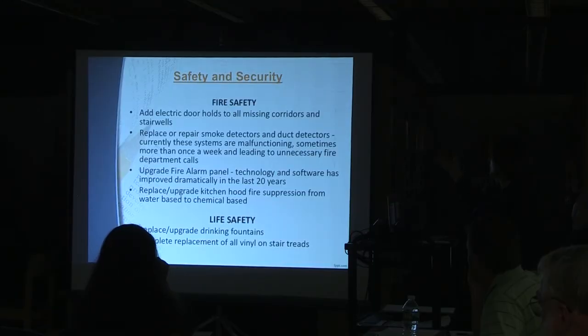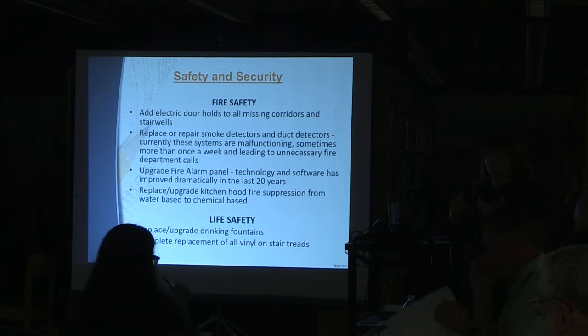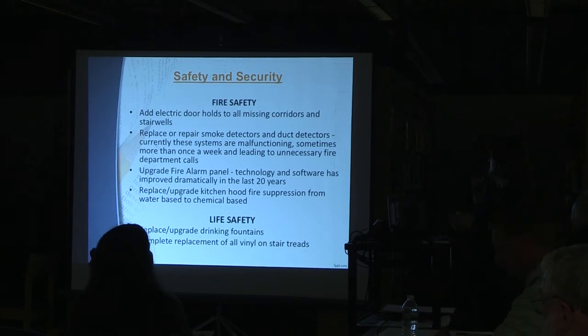We need fire safety electric doors to the corridors and stairwells because we don't have electric door holds for them. We also need to repair or replace smoke detectors and duct detectors. Currently these systems are malfunctioning sometimes more than once a week, leading to unnecessary fire department calls late at night. We need to upgrade our fire alarm panel—the technology and software have improved dramatically in the last 20 years, but we're still running on a totally different, obsolete interface.